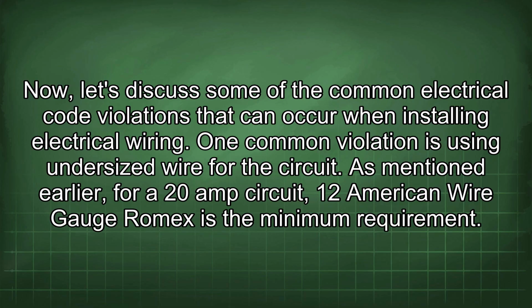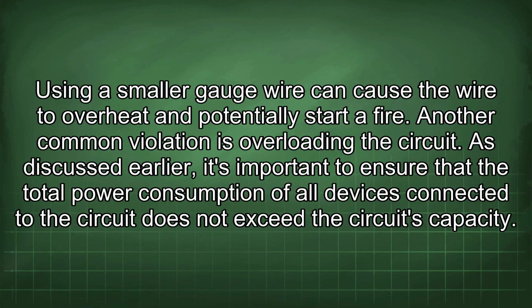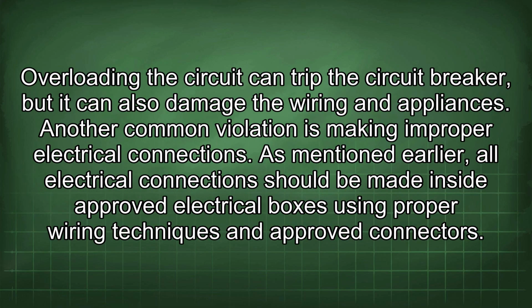One common violation is using undersized wire for the circuit. As mentioned earlier, for a 20 amp circuit, 12 American wire gauge Romex is the minimum requirement. Using a smaller gauge wire can cause the wire to overheat and potentially start a fire. Another common violation is overloading the circuit. As discussed earlier, it's important to ensure that the total power consumption of all devices connected to the circuit does not exceed the circuit's capacity. Overloading the circuit can trip the circuit breaker, but it can also damage the wiring and appliances.